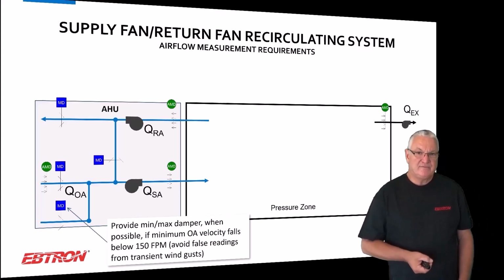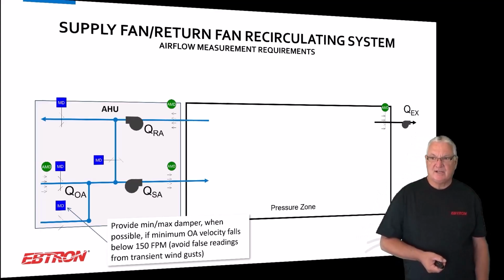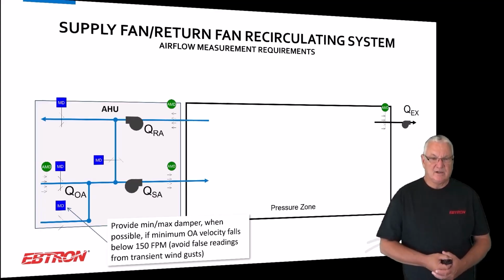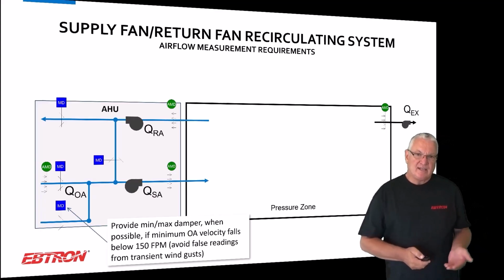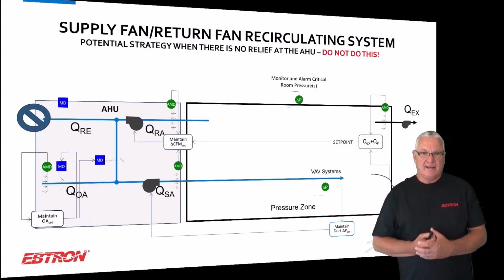It's not a limitation of the flow measuring device. We'll measure down to still air. You don't want to control 20, 30 feet per minute, and even if you could, when the wind blows, it would affect it. So that's why we have that kind of guideline there.